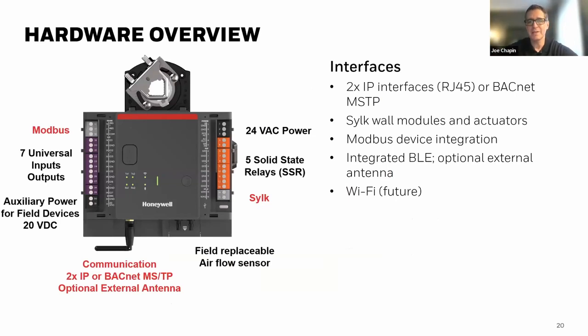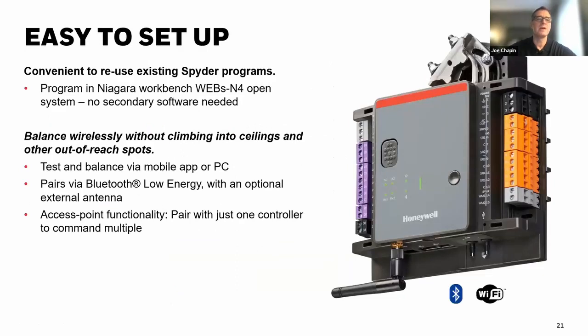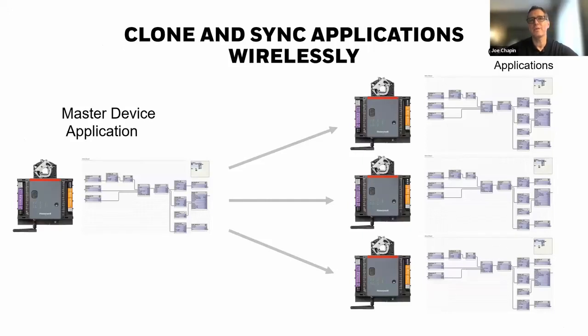You also can balance it wirelessly. So what that means is I can plug the device into my Niagara Workbench, write my control sequence on the original device, and install the device. I can test and balance it via the mobile app or the PC if I want to. Again, that could be wireless if you want to. Then I can clone and send out the control sequence to all the subsequent devices. So think of the amount of time you're going to save, compared to the old way of plugging into each device with the laptop; now I can do one device and send it out to multiple devices and clone it. This also works for upgrades as well. So very great functional device, and the built-in actuator is kind of the cherry on top of that.